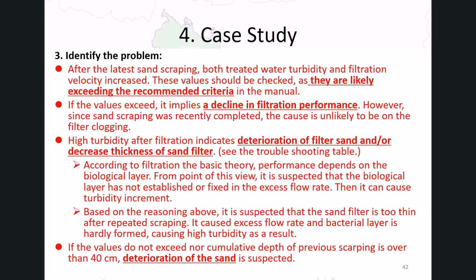This also suggests that the sand layer may have become too thin after repeated scraping. If the total removed sand depth exceeds about 40 centimeters, the design sand thickness is no longer maintained, since that is the standard of the layer thickness, and you will see inadequate thickness with high possibility.